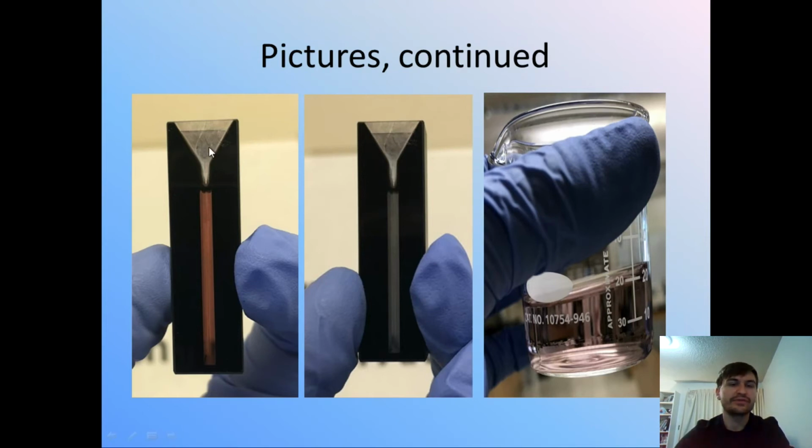So we use a microchannel cuvette. That's what this glass square is. It's like a rectangle. It's black on the inside to minimize internal reflection. We want light going straight through it, not bouncing around. And if you can see here on the top where the triangle is, there's a little bit of purplish haze. That's actually gold that's been plating onto the glass. And so we clean these periodically with aqua regia as well.